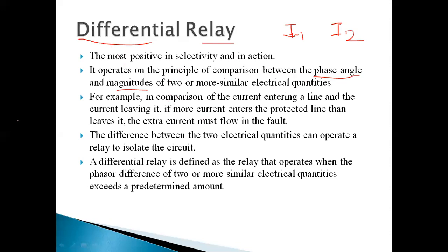For example, in the comparison of current entering a line and current leaving it. If we are considering one circuit in which current is entering at one end and leaving at the other end, if more current enters the protected line than leaves it, the extra current must flow in the fault.